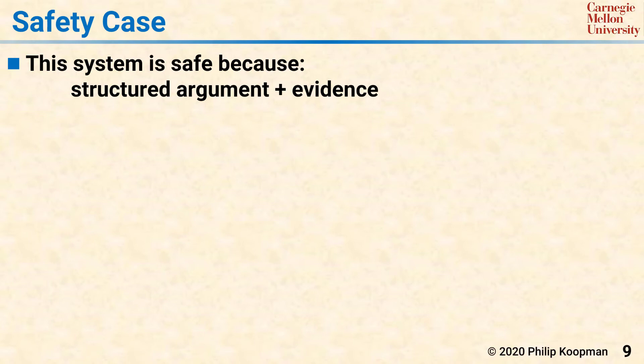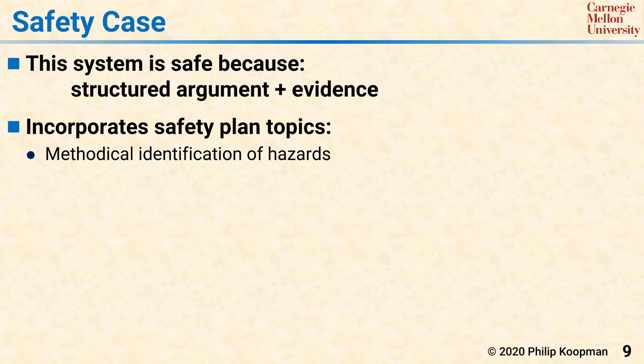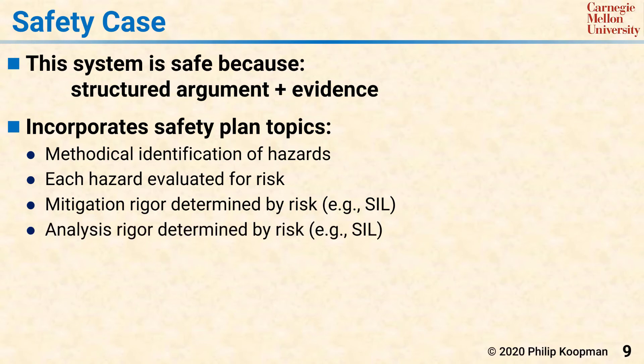Thus, the safety case will incorporate written descriptions and evidence for at least the following: a methodical identification of hazards, an evaluation of each hazard to determine its risk, appropriate mitigation and rigor used as determined by the risk's SIL, and an analysis, testing, or other means to ensure that mitigation was actually completed successfully.